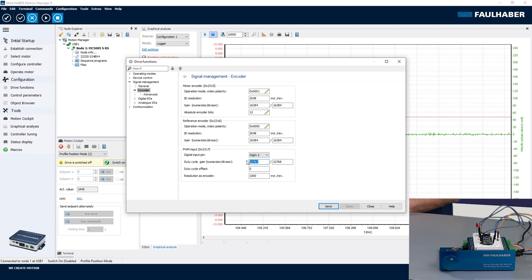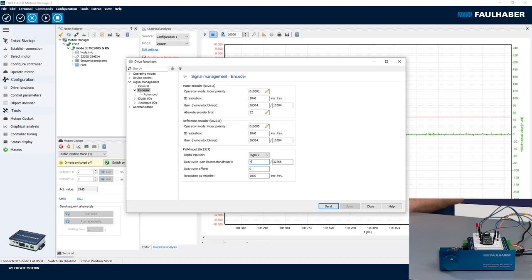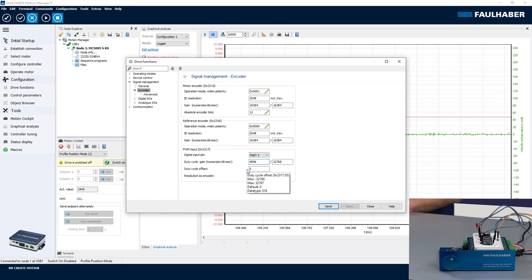And here the numerator of my gain would be the increments that I want my drive to move on a full range of my dial. For a single turn, for example, it would then be entering these 4096 increments that we are calculating out of the linear hall signals of these brushless motors. Of course I can also add an offset here if I want to have a positive and negative direction, but I'm not going to do this right now.